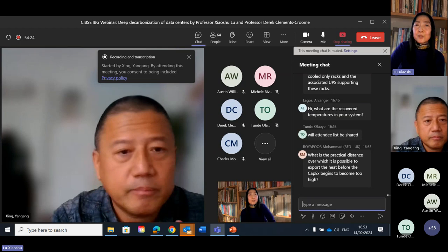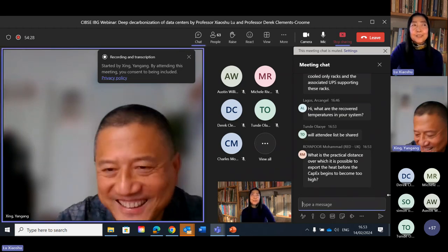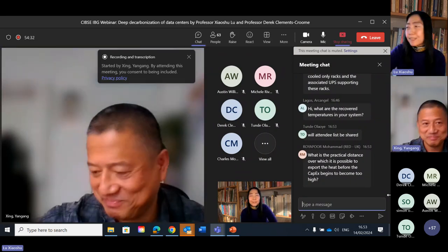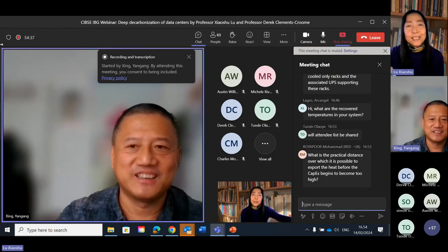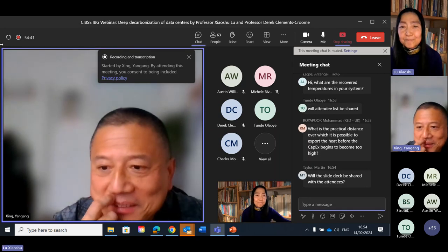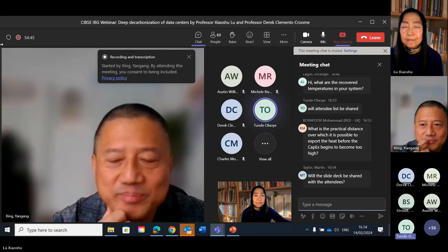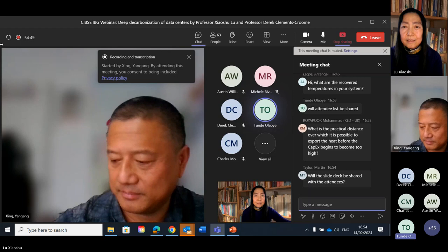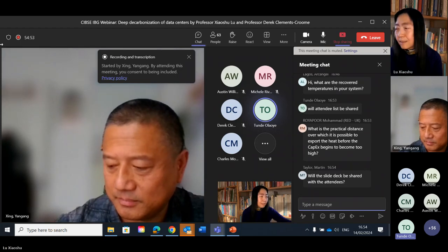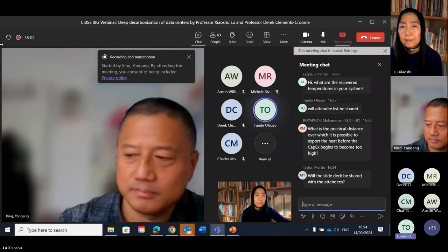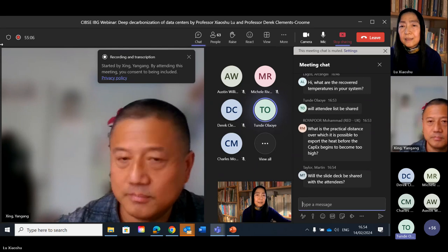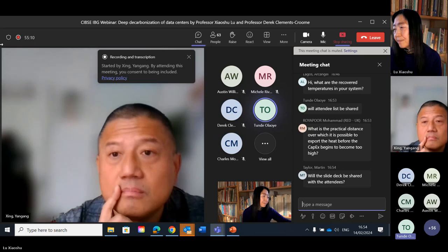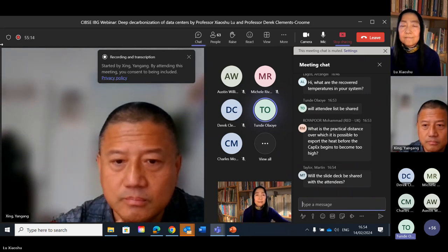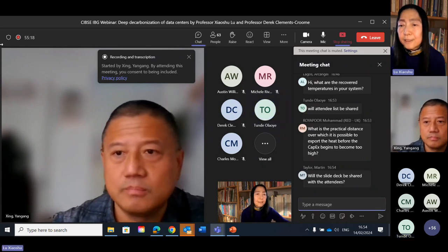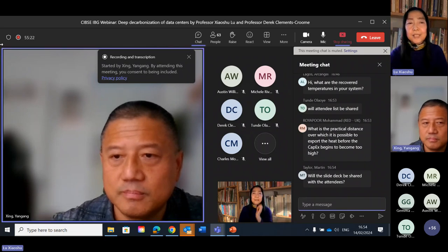But I have one interesting question for you for the UK. Because you normally use boilers to heat the building, what is the return temperature if you use a boiler? Typically in the UK, we normally have flow and return in peak winter about 70 and then coming back it's 60. We're trying to push down to 75, 55 on newer buildings. Older buildings can be 80, 70 sometimes. So it varies on boiler design. We're not very good technically about managing delta Ts across buildings. So it's quite varied depending on which building you go to, but we are trying to push for condensing boilers to be lower, and then with heat pumps obviously that's dropping a bit further. Okay, thank you. So it's much higher than the return temperature in Finland.